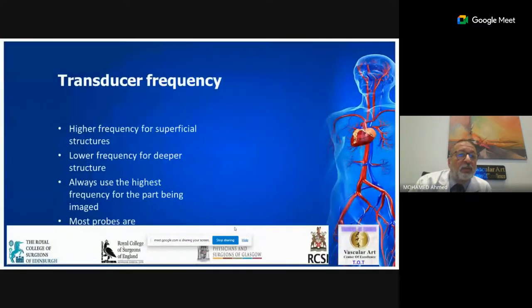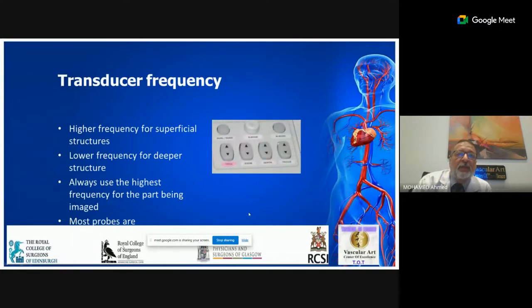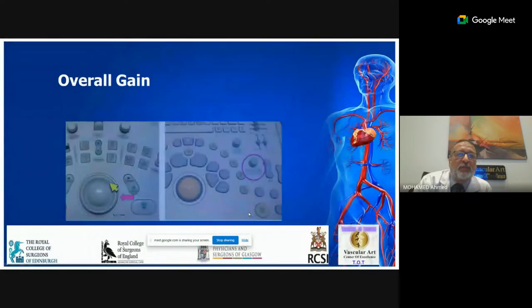This is the transducer frequency. It goes between 2 to 3 megahertz for the abdomen, lower frequency, or it goes up to a very high frequency, like for the digital arteries, up to 12 and 15 megahertz probes. This is the transducer, multiple transducers with multiple frequencies.